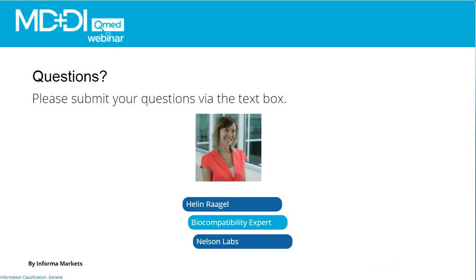So, Helen, we've got quite a few questions coming in. Our first one for you: what are your thoughts on evaluating end-of-device life cycles on aged samples just by a cytotoxicity test? Yes, that's a great question, because with the submission to the MDR, for example, it has now become really a key question, right? And I do understand that we don't want to have everybody undergo all of the testing again to demonstrate that, yes, your device at the end of shelf life is still biocompatible. So what we have developed as a strategy here is to use the highly sensitive nature of the cytotoxicity test as an initial screen, and then compare the device at the end of shelf life versus the newly manufactured device.